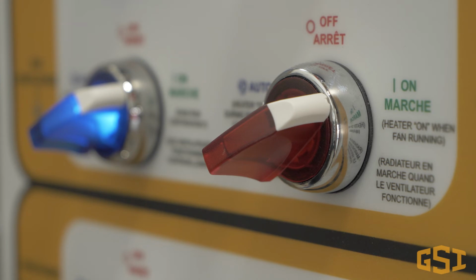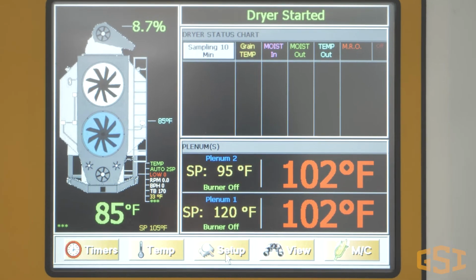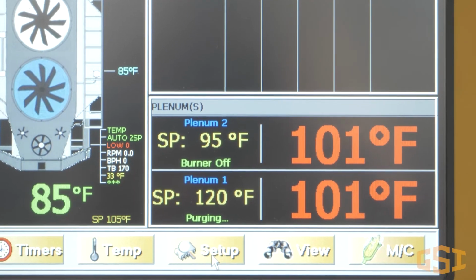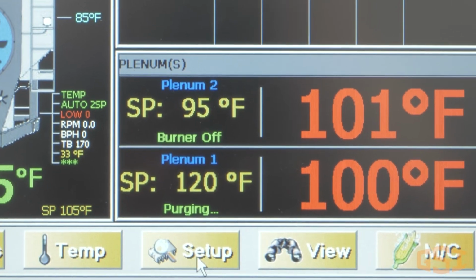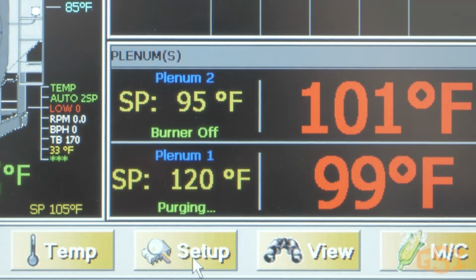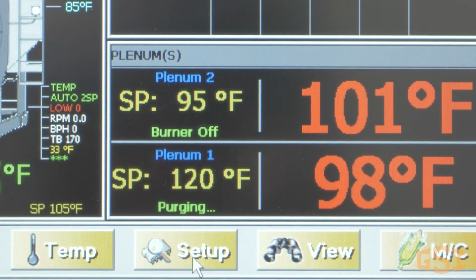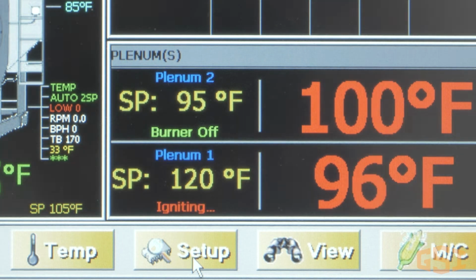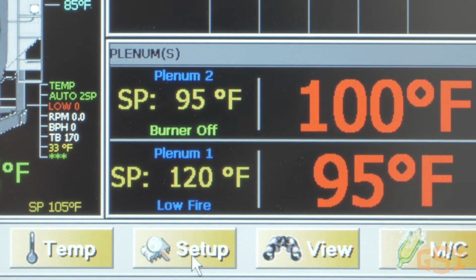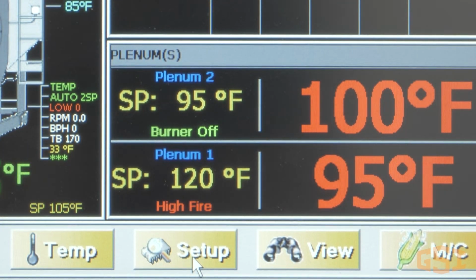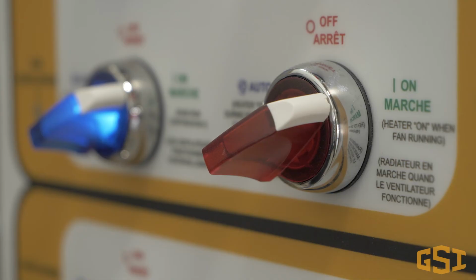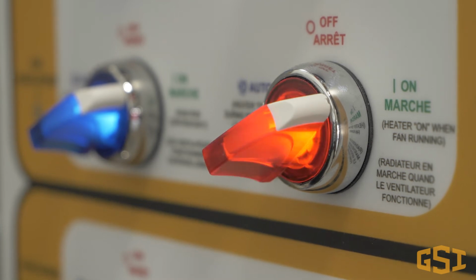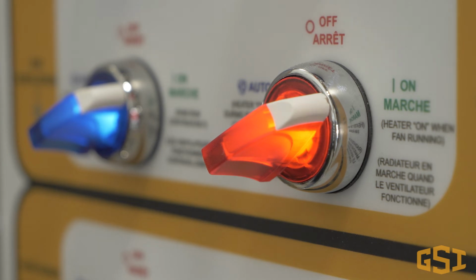Here's how it works. After the fan is running, turn on the burner switch. The burner will go through a 10-second purge delay followed by burner ignition. The length of the ignition time is about 4 seconds. During the 4 seconds of ignition, the red light in the burner switch will turn on. Once the ignition period of 4 seconds ends, the light in the burner switch is used to identify flame detection. If a flame is detected, the light will stay on. The light in the burner switch is the easiest way to tell if the flame probe is physically touching the flame.